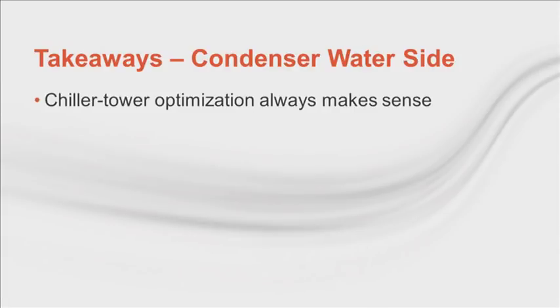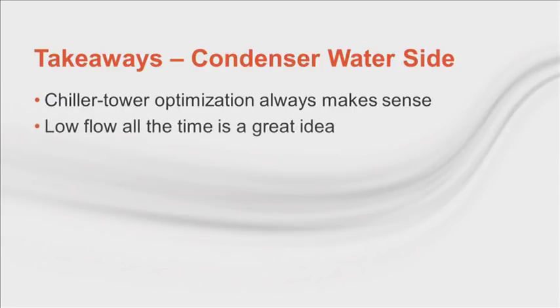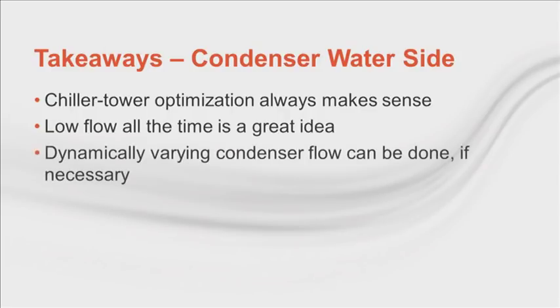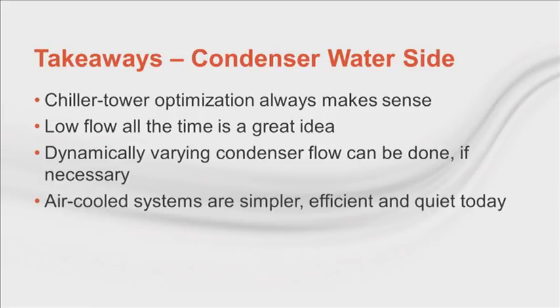Now, summarizing the condenser side of the system. Chiller tower set point optimization is very important, especially if the tower and chiller are variable speed. Again, for new systems, there's a great benefit lowering the flow rates, whether all the time when the flow is constant or some of the time in the case of variable condenser flow systems. For existing systems with high design flow rates, like 3 GPM per ton, dynamically varying the condenser flow allows for some of the condenser system energy savings without requiring a new chiller. Air-cooled condensers, especially when packaged as air-cooled chillers, simplify things a lot. Advancements in compressor, heat exchanger, variable speed components, and controls have made air-cooled chillers more efficient and quieter in recent years.